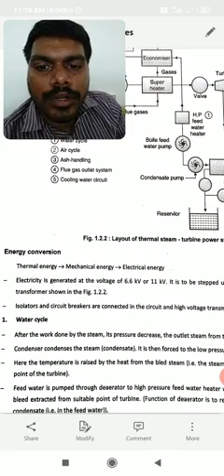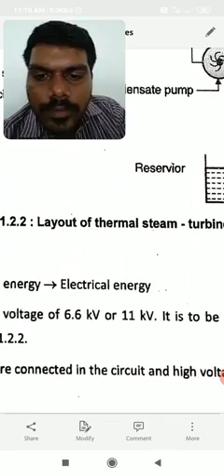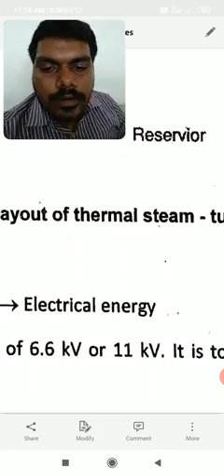We will look at what energy conversion is, right? The thermal energy of the steam is converted to mechanical rotary energy in the turbine, and then with the help of a generator it is converted into electrical energy. The generator voltage is always 6.6 or 11 kV, not more than that. At 11 kV and 6.6 kV the current is very high, so we don't want to send very high current through the transmission network to the load, so we need to step up that voltage. So we need a transformer, and the transformer section will come.